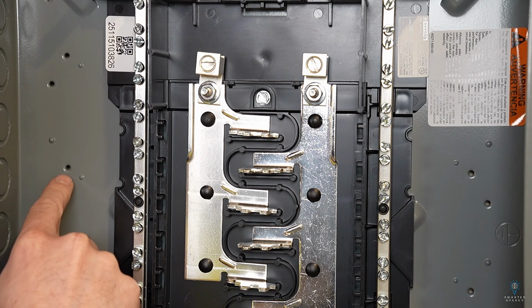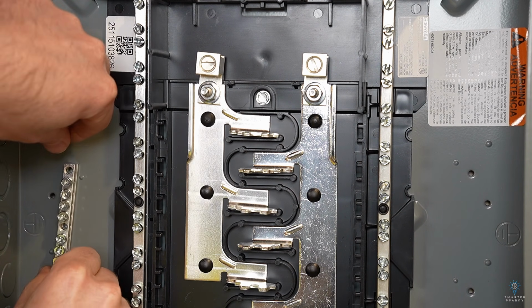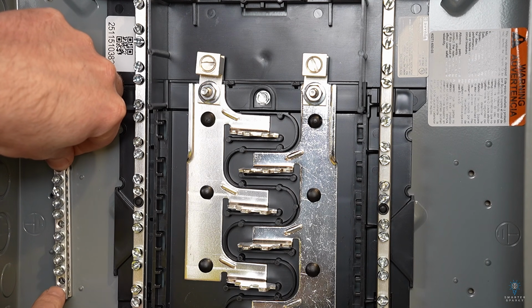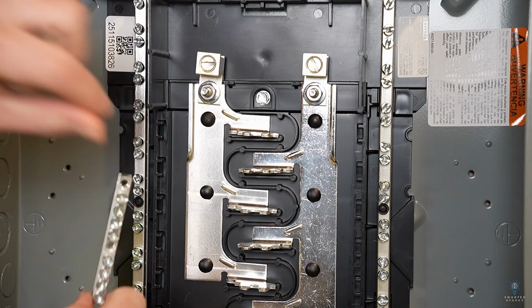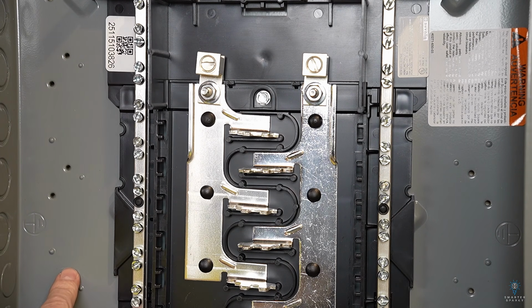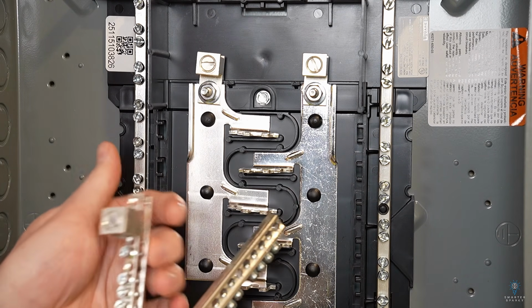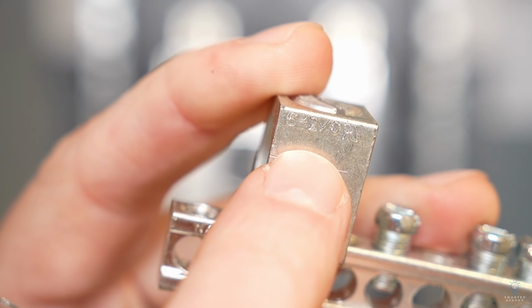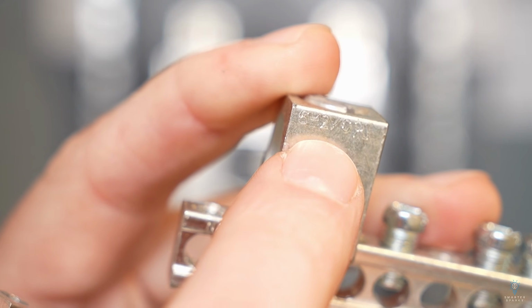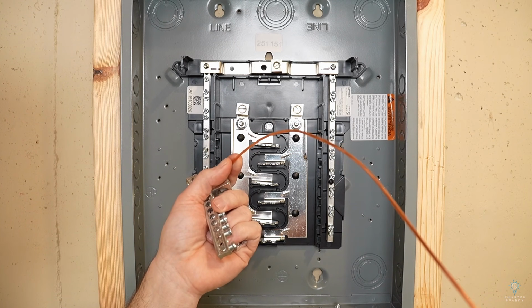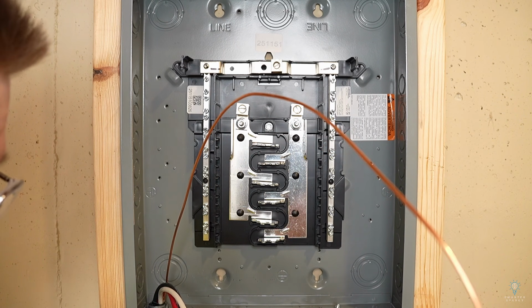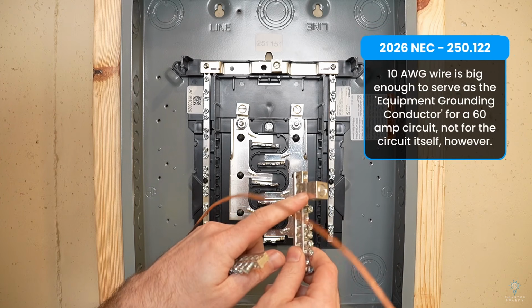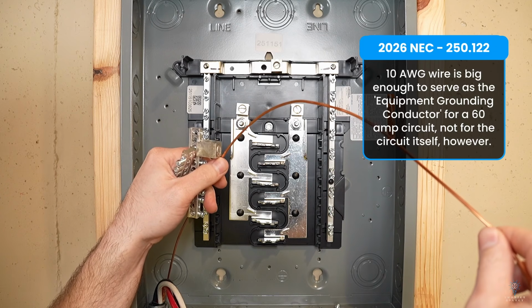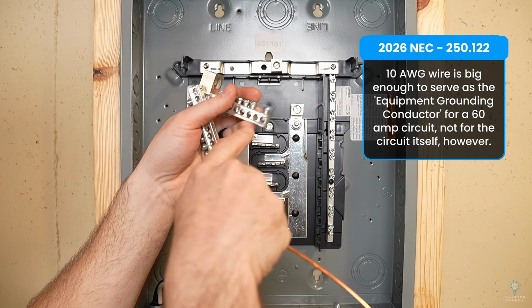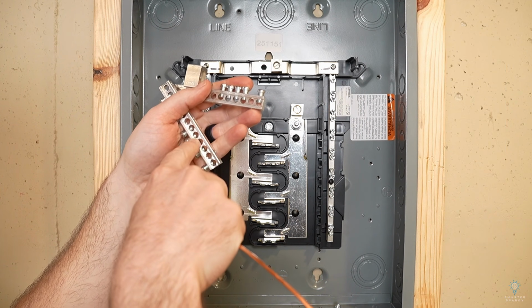Or right next to it, there is another set of holes that we can line up at the top, and then we can line up the bottom, and we can install 2 screws. I'm going to opt for the 2 screw system. You could go for the 1 screw system as well. In my opinion, having 2 screws sounds like a lot better of an idea. Notice this ground lug is only rated from 6 gauge through 2/0 gauge. So that means that this 10 gauge ground wire, which is big enough for 60 amps, will not fit in this lug. So we're going to have to land this ground wire inside of one of these holes in the side of the ground bar.